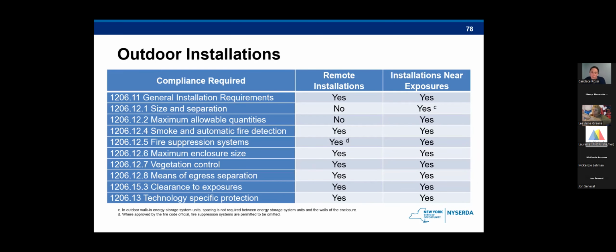So once again, we have this chart that's provided in the code. Remote systems may not have the same requirements as other outdoor systems. These remote systems will not have the same life safety risk factor involved, so their requirements may be a little less stringent in some areas. You can note in the subscript on the suppression system that for remote installations approved by the fire code official, fire suppression systems are permitted to be omitted. Once again, that'll be a conversation between the applicant and the fire code official to make sure there's a plan in place. So they can allow for that suppression system to be removed.